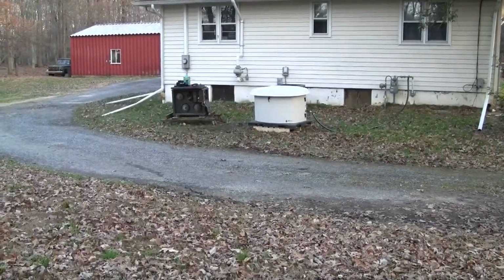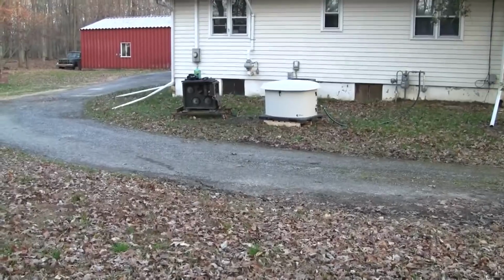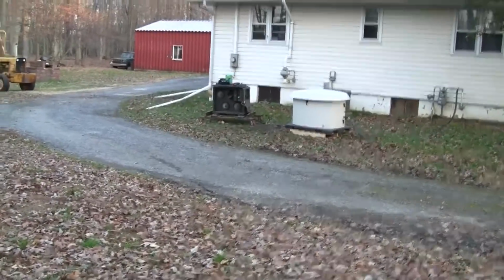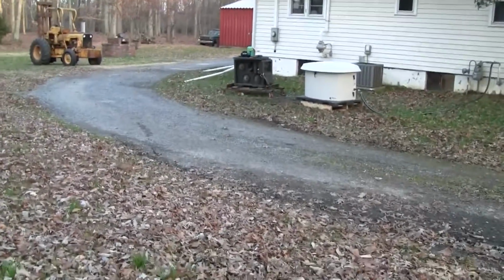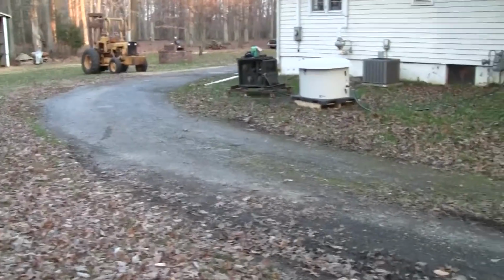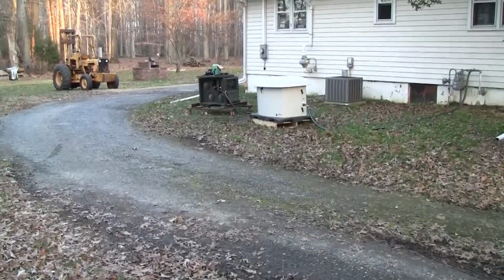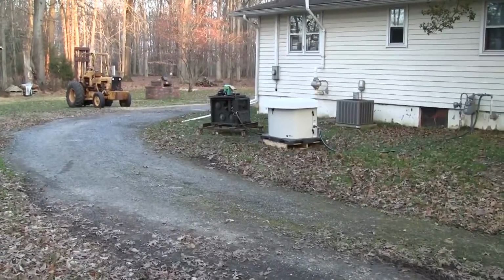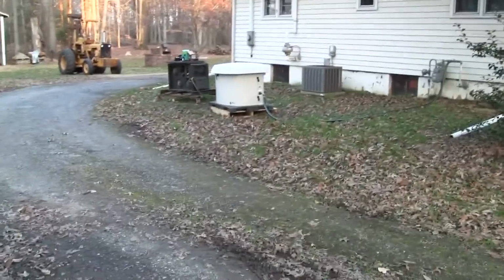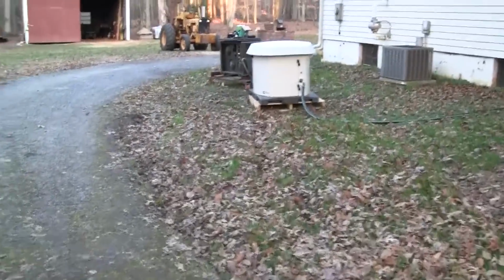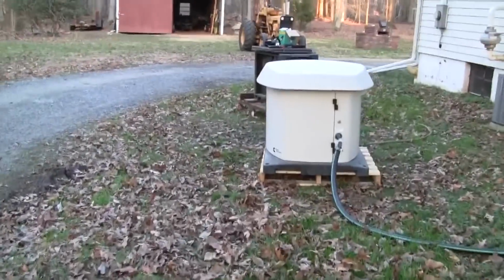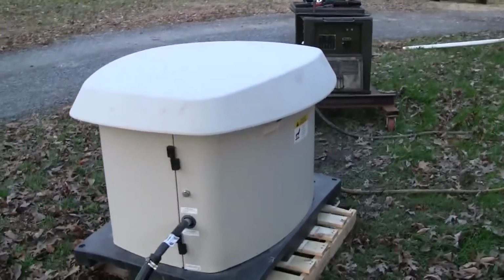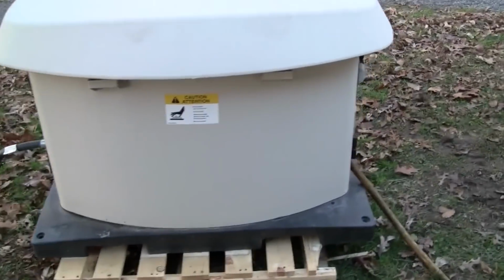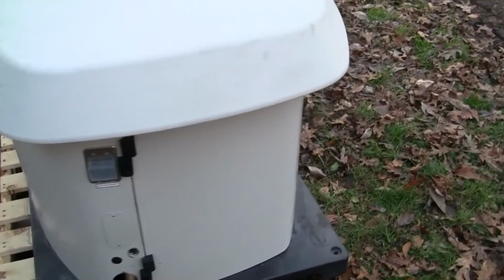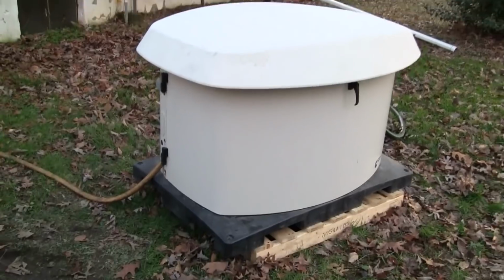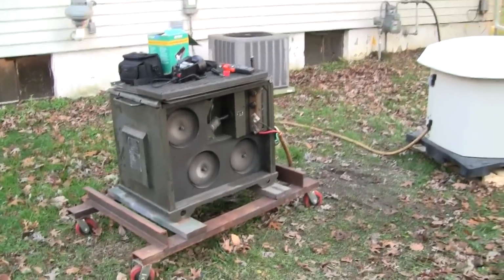Well, I'm standing about 30 feet away from the generator. And this clip is just to give you an idea of the noise level. It's really not that bad. I mean, if you were in a residential neighborhood, it'd be a little annoying. Now, mind you, it is at 15 kilowatts, so it's at 75% of rated capacity right now. You've got the noise of my load bank as well, so it's not all the generator.